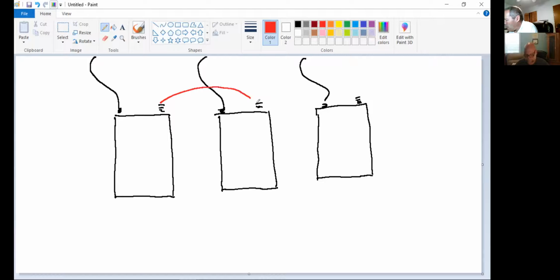I'll ask this, this came up before. On closed delta, this came back from the transmission lines when they use delta, they don't have a neutral. Why do I float the neutral? What's its purpose as far as three-phase is concerned? Does it share load between all three transformers? It keeps all the transformers in sync with each other. When you say synchronization, you're right, very close to it. It's what they call load sharing, right?